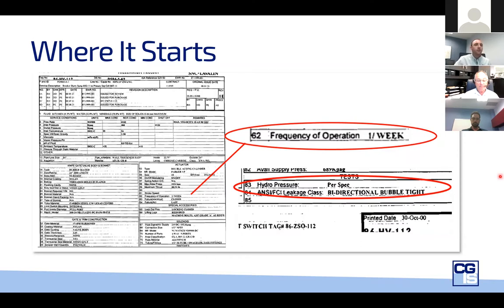For a valve that will stroke very infrequently, you may need to increase the actuator size in order to break through any scale or seats becoming fixed. Conversely, for a valve that will stroke very often, there are other considerations like upgrading the trim, seals, or actuation to handle high cycles. One small issue with this data sheet is that it doesn't tell us what type of bidirectional isolation is required or what standard that needs to be tested to.